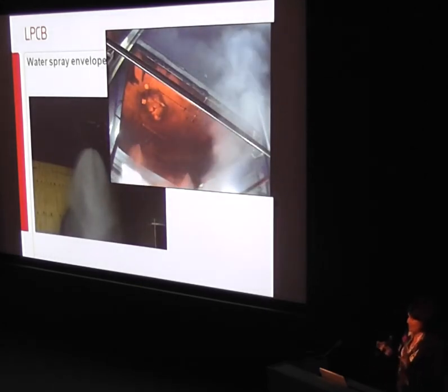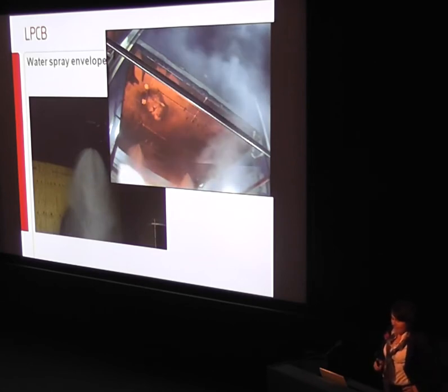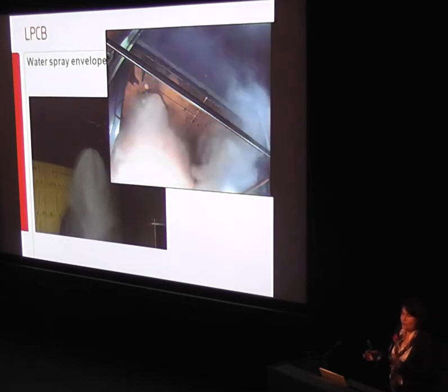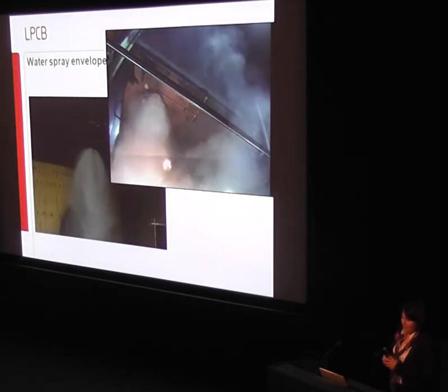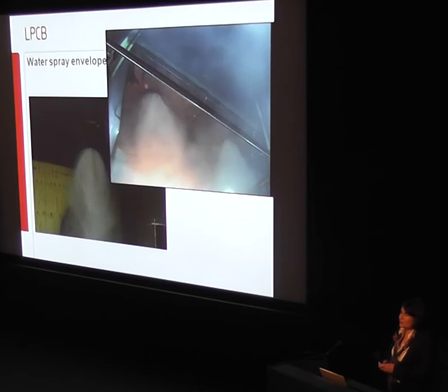So we haven't seen many videos, so I'm quite pleased to be the first to get a video working. This is a picture of a water mist nozzle. It's like a sprinkler one, but as I said, they're usually charged at a higher pressure, so the water is forced out of the nozzle faster, and there are smaller orifices, so the holes that they go through are smaller.